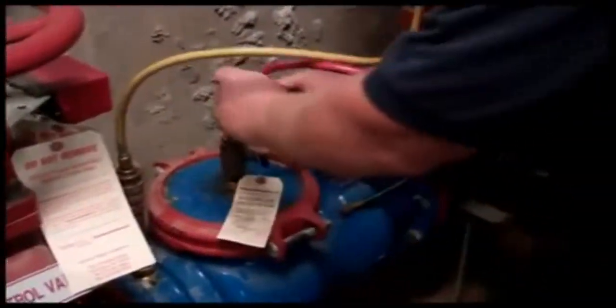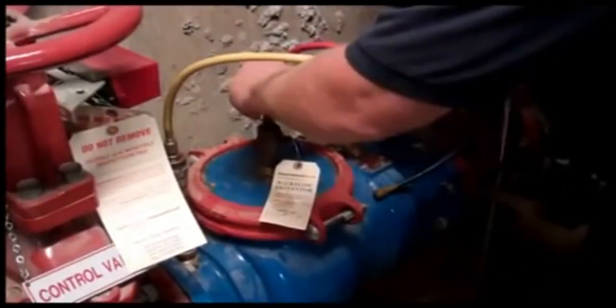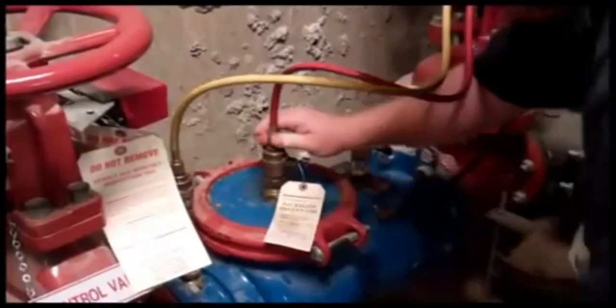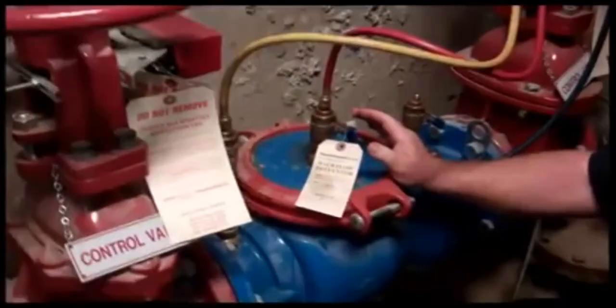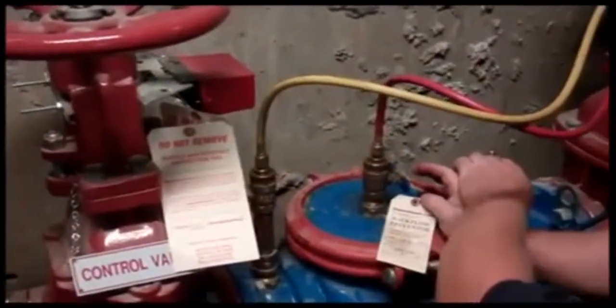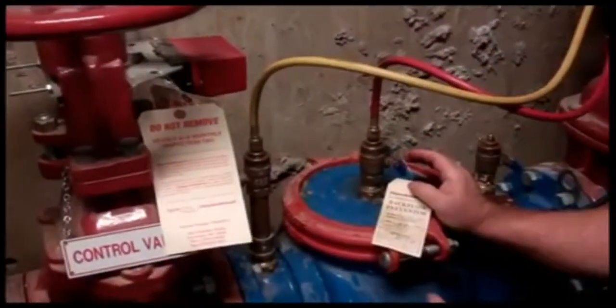The technician connects two of the tubes from the backflow test kit to the backflow. This is going to be used to verify the pressure difference on the supply side and the discharge side of the first check in the backflow preventer.